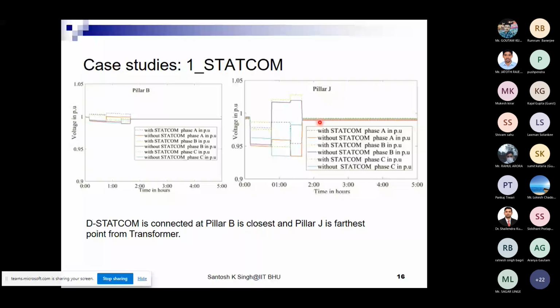So STATCOM is helping at the extreme ends, but at the closer ends, it's creating an over-voltage situation. This is going to create problems for transformers, because you have to consider wherever the location of the STATCOM is, it's going to affect over-voltage at the transformer sitting close to the substation.